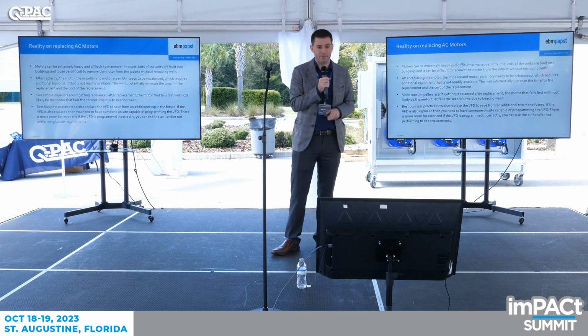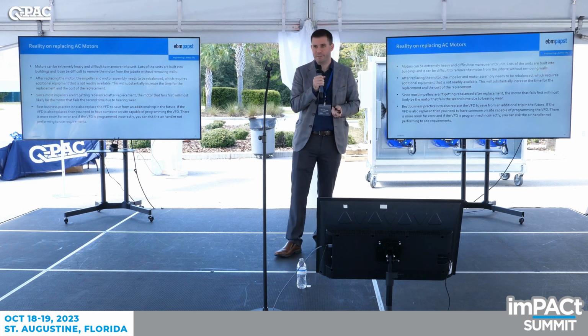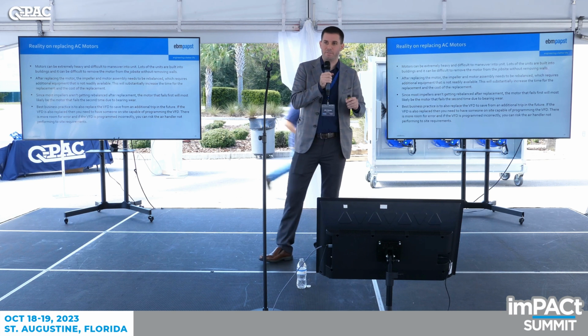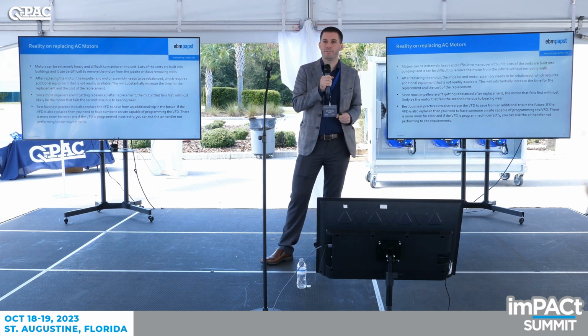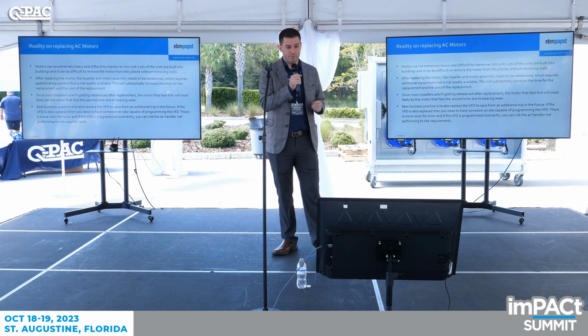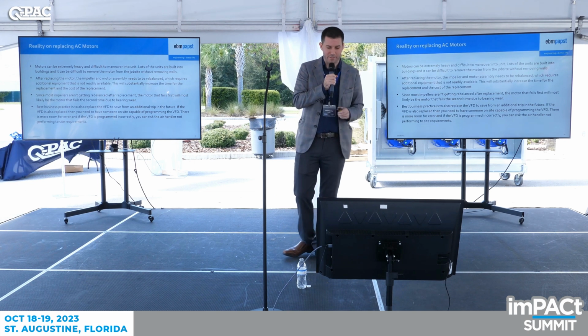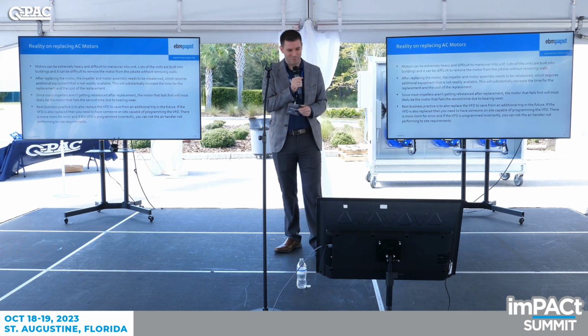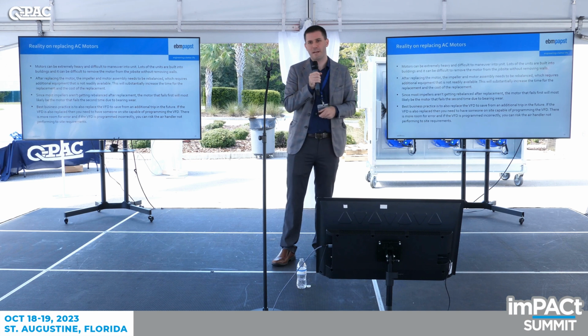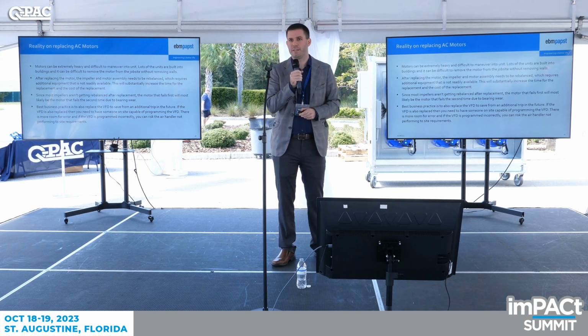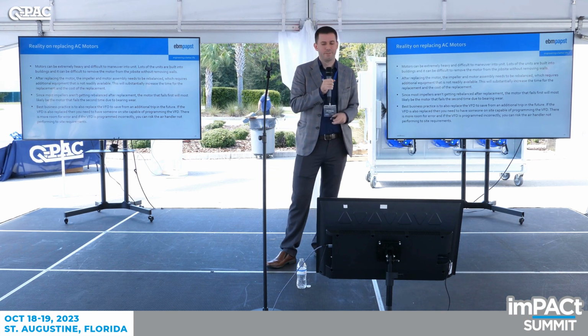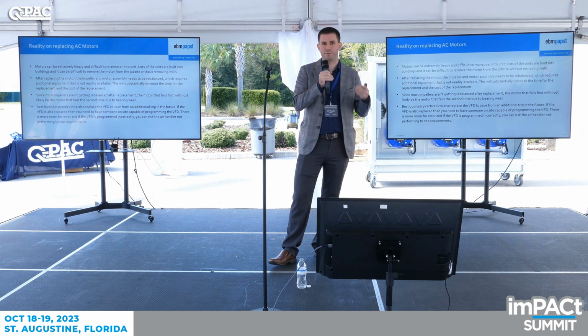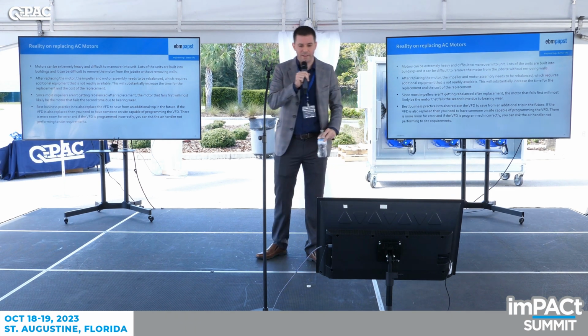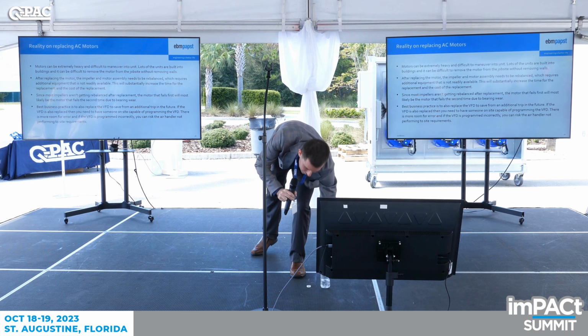After replacing the AC motor, if the impeller and motor aren't rebalanced together, that first fan that failed is almost always going to be your second fan that fails. And since most impellers aren't getting rebalanced, that's the first fan that fails, this is the second fan that fails. And the best business practice is also to replace the AC motor with the VFD, just because the VFD life is right in line with the life of the AC motor.